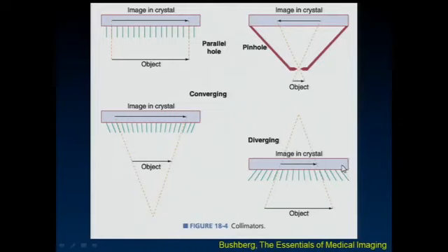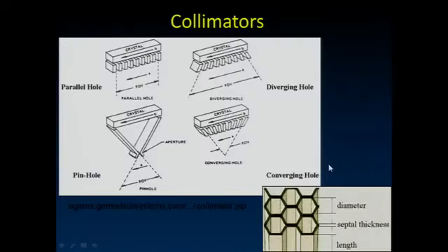You know, where you have a fairly small camera. So we used to have a portable nuclear medicine camera that we sent up to the intensive care units to do portable VQ scans. There the camera was relatively small, but we needed to see the large field of view, the chest. And so the collimator on there was a diverging hole collimator, which took that large field of view and really brought it down to the size on the face of the camera.